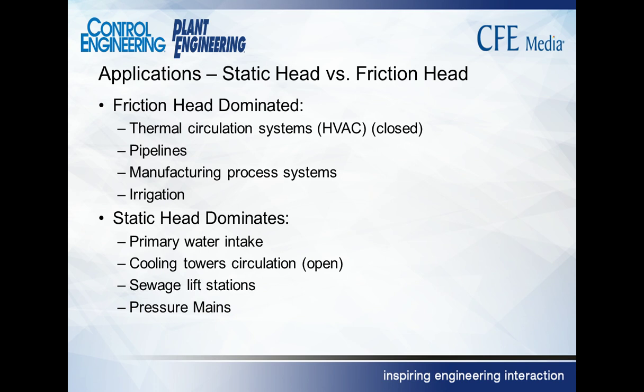Friction head dominated system. The typical one is a thermal circulation HVAC system. I'm pumping chill water, I'm pumping hot water. And I might be pumping it in a building up 3 or 4 floors, but it comes right back down through another pipe, that same 3 or 4 floors. So net, there is no elevation change. I'm simply pumping the liquid around in a loop. So there's no elevation head developed.